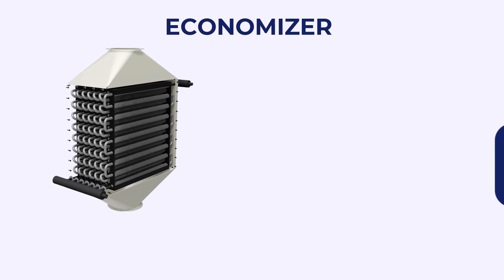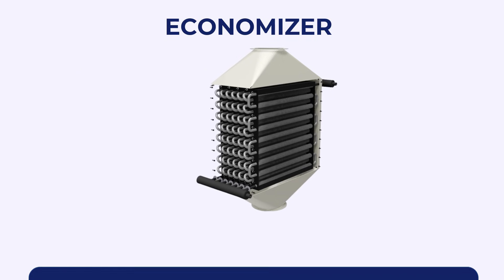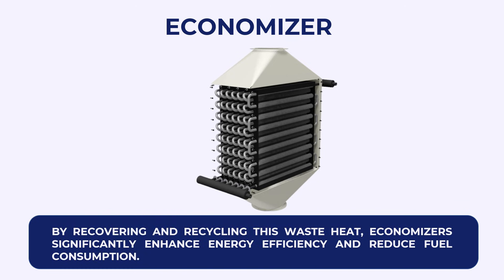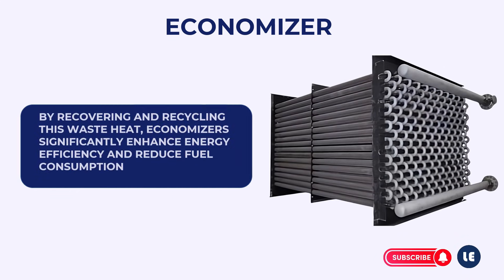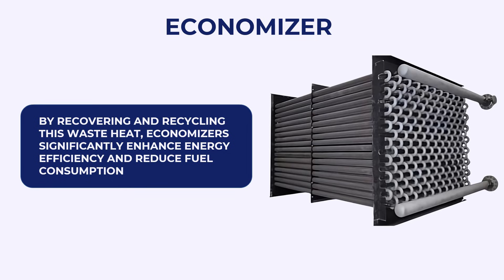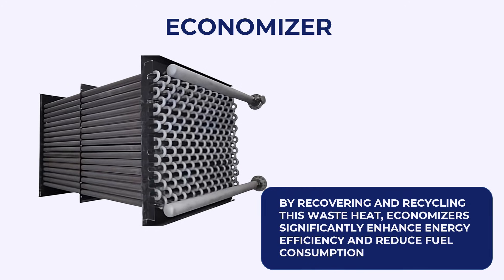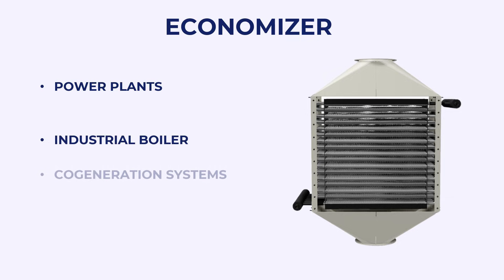Economizer. An economizer is a mechanical device or heat exchanger that captures waste heat from a system or process and utilizes it to preheat fluids, typically air or water, entering the system. By recovering and recycling this waste heat, economizers significantly enhance energy efficiency and reduce fuel consumption. By recovering waste heat, economizers also reduce fuel consumption and operating costs of boilers. They are commonly used in power plants, industrial boilers, and cogeneration systems.